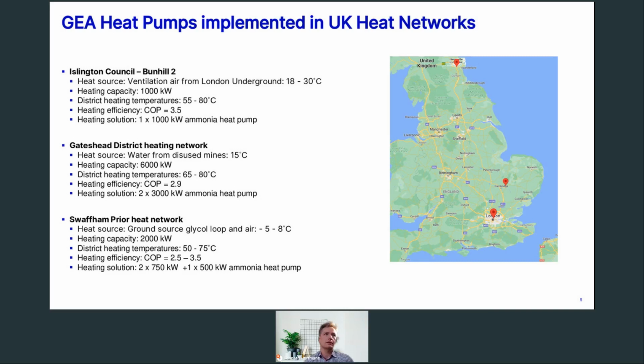The same is the case for Gateshead, near Newcastle, where we also supply 80 degrees. But in this case, we are taking the water from a disused mine that has filled up with water. So it's nice and warm. The mine water is now 15 degrees. We cool it by around 6 degrees and pump it back down in a separate place in the mine, so the cold water is not going to go back into the heat pump loop. There is a good view of how the water is distributed within the mines, so where we are pumping the water back down is not recirculating back to the water we're using for the heat pump. In total this is 6 megawatt, 2 times 3 megawatt heat pumps installed there.